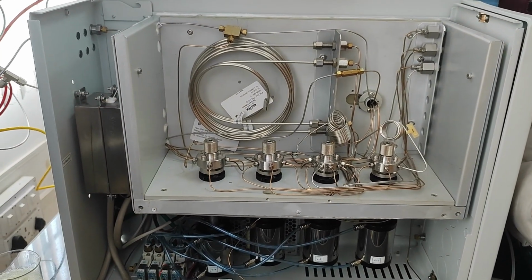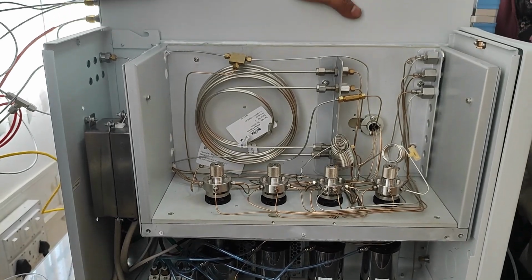If my sample contains a very high amount of CO and CH4, that will definitely give a peak in TCD, so there is no need to use the methanizer, because the methanizer will be consumed. Very high amounts of CO2 and CO will convert into a very high amount of methane, so our methanizer consumption will be higher. At that time we can bypass. This is the bypass valve. And this valve is separately for injecting into the FID line. So one is for injecting the sample to the TCD line, one is the CSB column switching valve, one is to bypass the methanizer, and one is for the FID line.